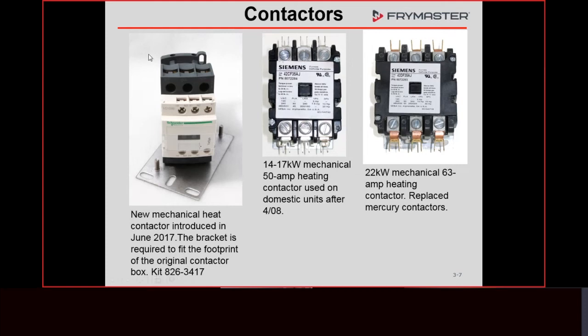The cycling we had going on would always pull these contactors in. So even if you were demoing a fryer, once we had mechanical contactors, if you had a 4-bank fryer, you had a symphony going on of clunking, because it would cycle on and off, then the other one would cycle on and off, just a continual clunking noise.